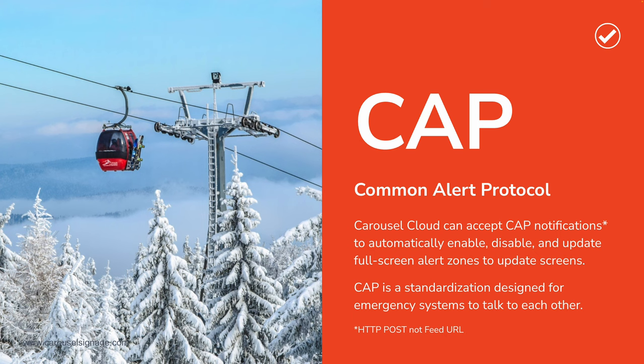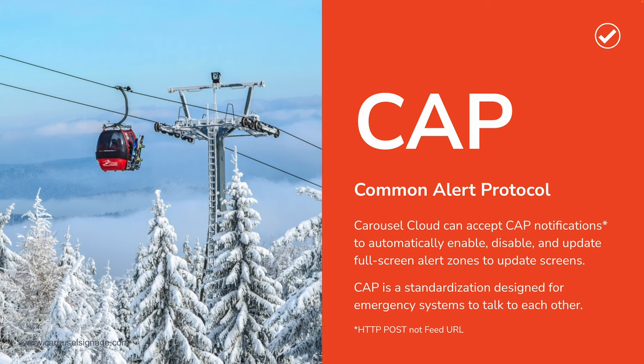That's what brings us to our primary topic here today, and that is CAP, the Common Alert Protocol. CAP is an open and standardized method for emergency systems to relay information between themselves, greatly reducing the technological barrier for integrations. This allows everything we talked about with manual alerts to happen, but automatically, without anyone needing to log into Carousel to turn on these alerts, because another system which is dedicated to life and safety is sending us instructions, and that is done via CAP.